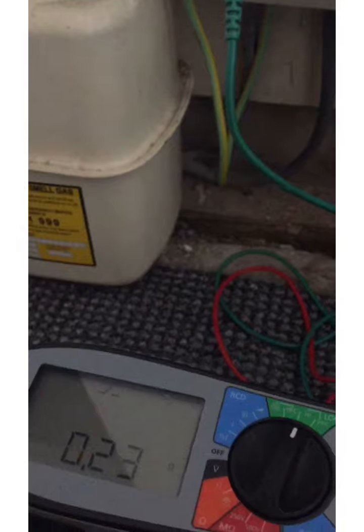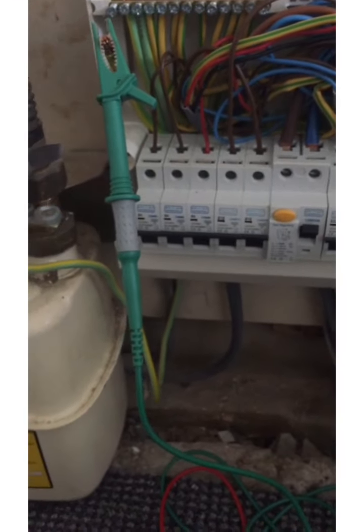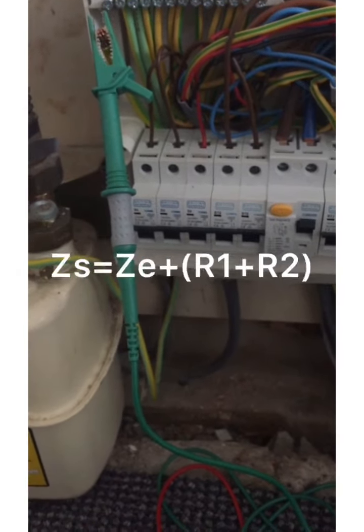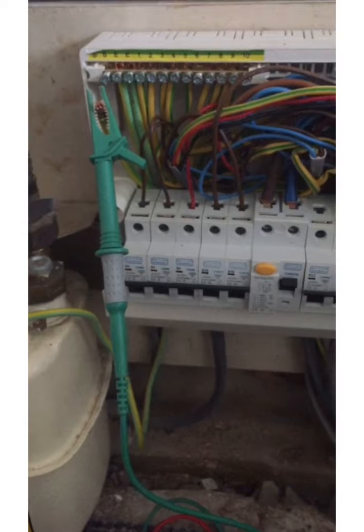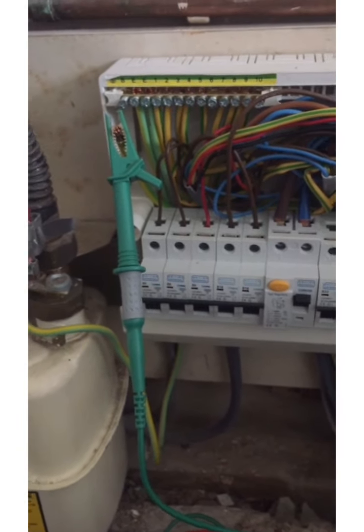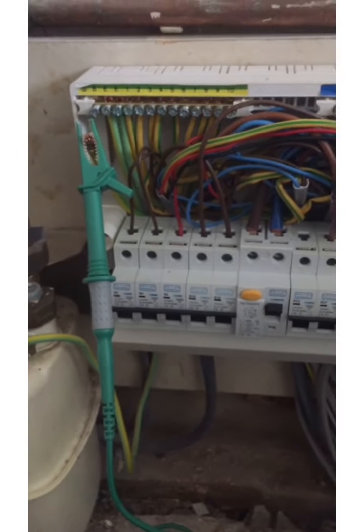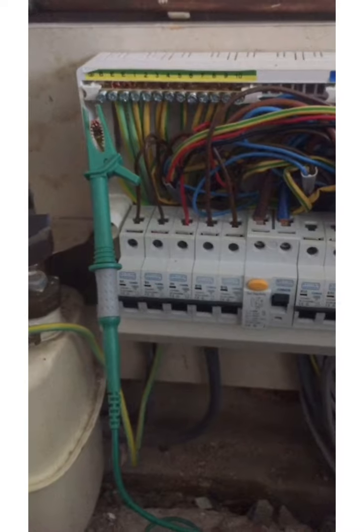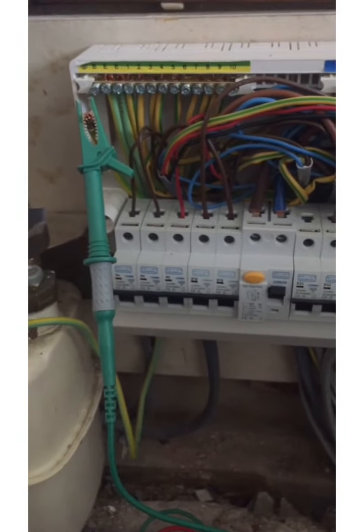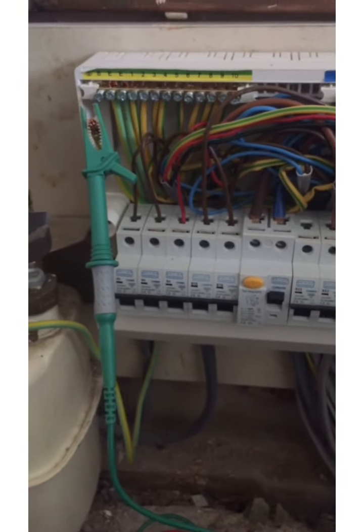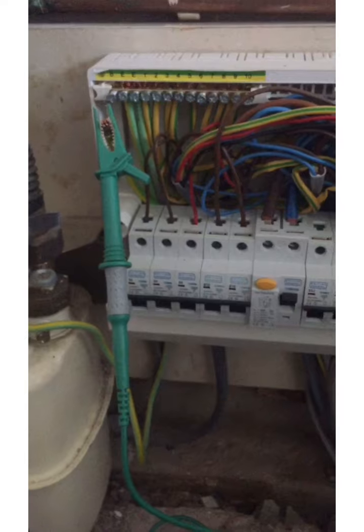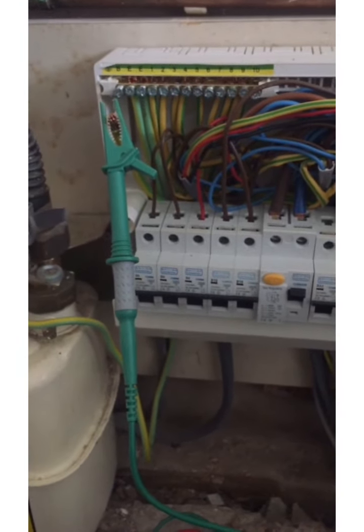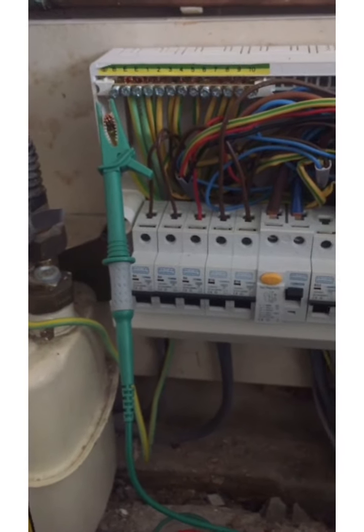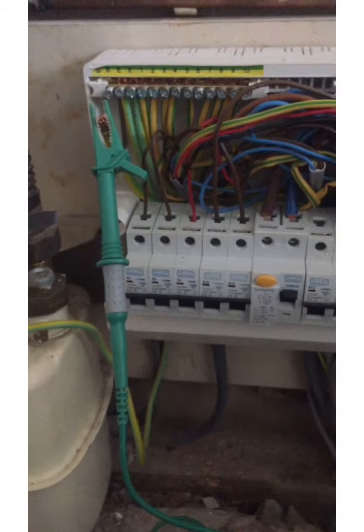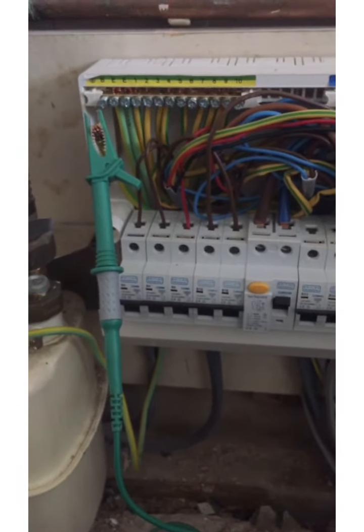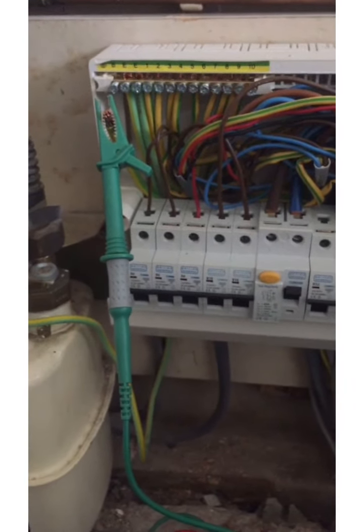What else to say? Once we've determined that ZE value, we can obviously then use that to calculate ZS. We could add that value to R1 plus R2 and determine our ZS that way if we choose to. And when we compare, I need to cover ZS on its own, really, the comparison or the verification of it. But when we compare the ZS values for the different circuits, something to realise is that we would only ever take 80% of a value in the regs, because that is at the operating temperature of the conductor, and the values in guidance note 3 and the on-site guide are 80% of what it says in the reg. So if you've ever looked at that and wondered why there's a discrepancy, that's the reason why.